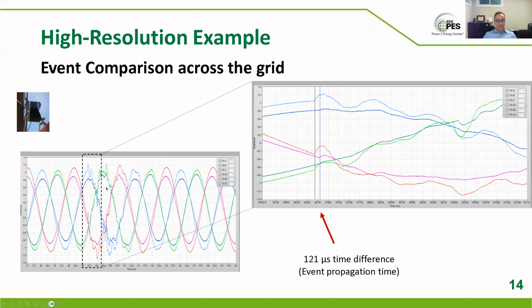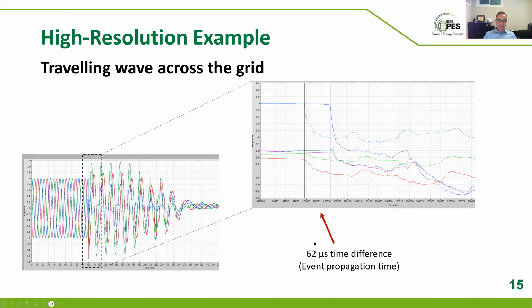Anyways, this is synchronized measurements at the two ends of the line. You can see a transient arriving; the light blue and dark blue again are the two ends, B phase, or you can look at A phase. They have different intensity, but the distortion, you can see they have a 121 microsecond time difference. This line, by the way, if the traveling wave or the disturbance had started at one substation, from previous measurements we know it takes about 204 microseconds to get to the other end. So we know since this time is less, the event must have happened somewhere in the line, not in the middle. If it was in the middle of the line, it would arrive at the two ends at the exact same time, so the time difference would be 0. But this basically allows an event location, whatever disturbance caused this, whether it was a switching, arcing, something that happened, based on this 121, we can locate what location on the line it was.